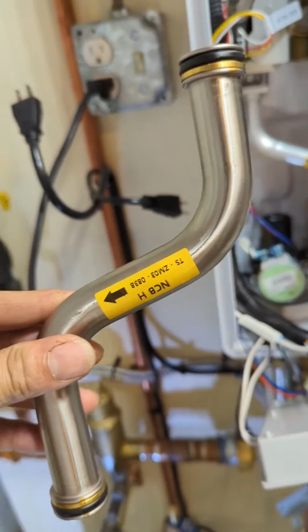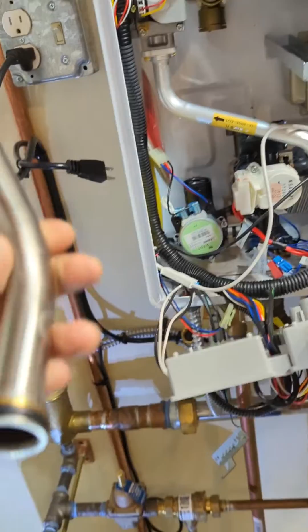So on this one you have to make sure you're in the correct flow, because this is supposed to go back down to the mixing valve. Make sure that's all clean, gasket is good, or o-ring. Then to put it in, since you have no play in it, you have to push it down first, all the way down, then spin it to the inside, then push it up, then you can lock it. Let me do that right now.